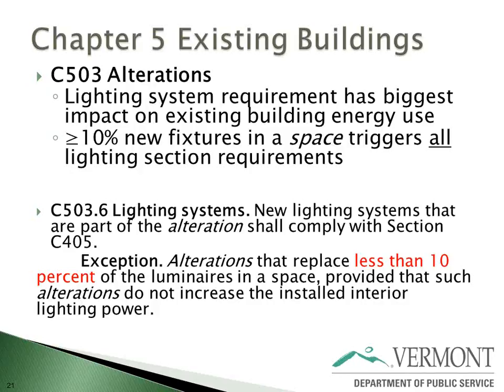Each section is now expanded and separately handled. The slide I have here talks about the alterations section, section 503, and the lighting systems part. This change from the existing code now says that if you do an alteration and replace less than 10% of the luminaires in the space, you're exempt. But if you're replacing more than 10% of your fixtures in a commercial space under a qualifying alteration, that space needs to come into full compliance with the lighting section of the code. So it needs to meet the lighting power densities, watts per square foot, the lighting controls requirements, and so on. That's a pretty big change, and I think the quote I had before was really getting at that—a lot of these big lighting retrofits would still do maybe less than 50% in a given space, so this is just getting at more efficient electrical lighting use in existing buildings, and that will get at some energy savings.